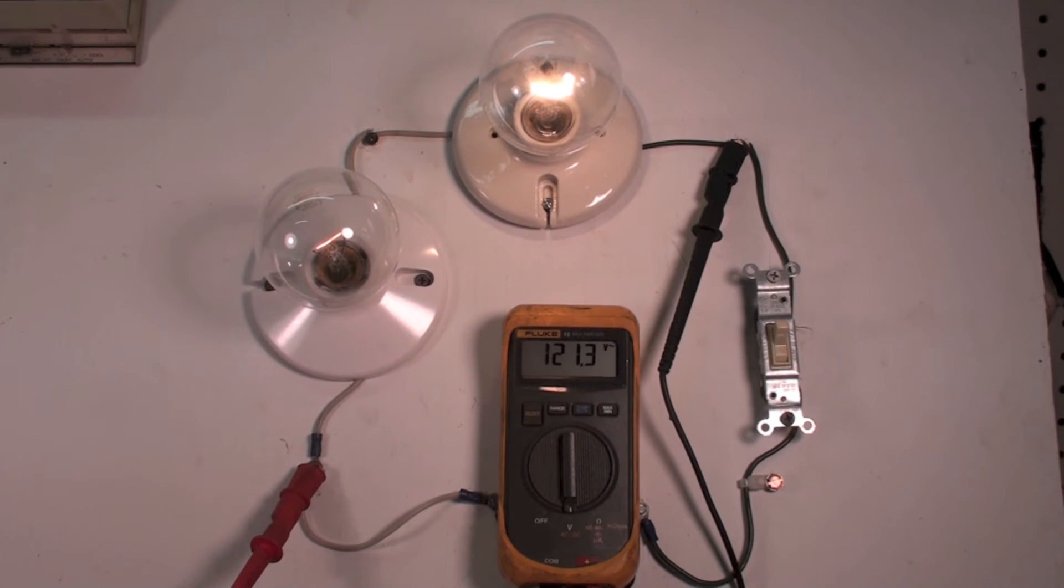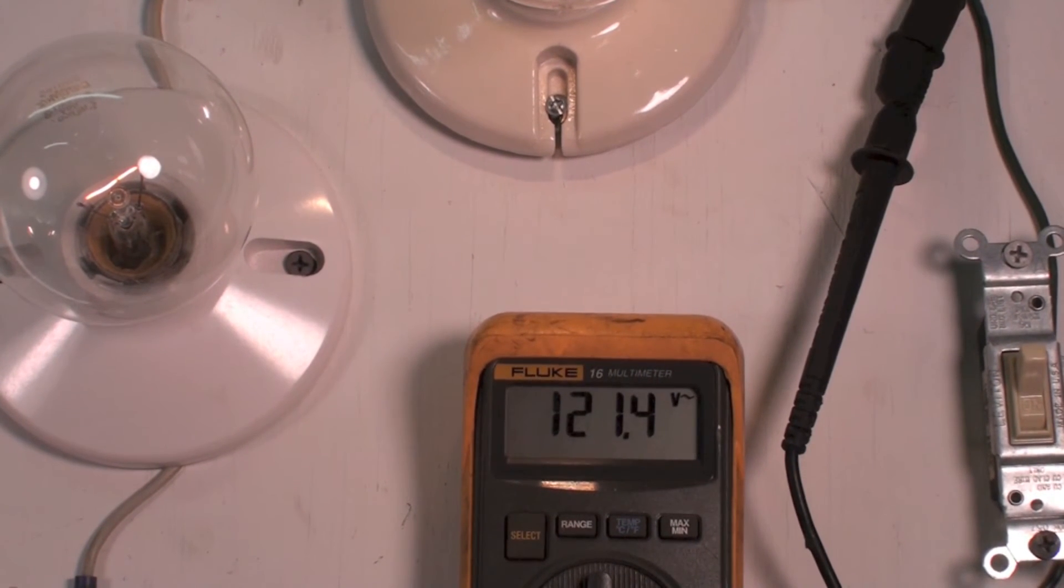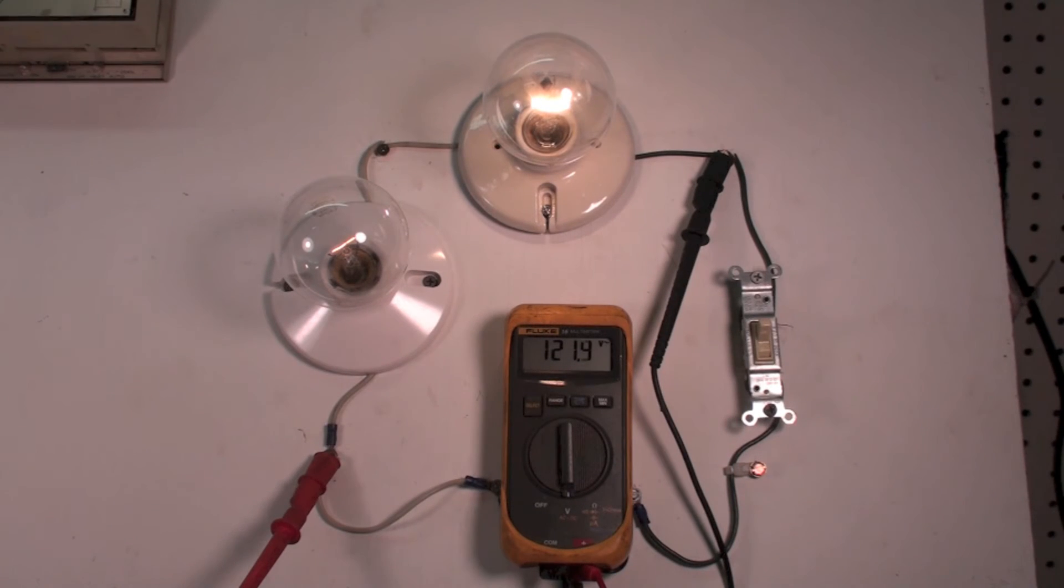So I'm either side of line, I am actually in parallel with these two loads, and I'm reading 121.3 or 121.4 volts. That's normal because I have 121 volts drop across this circuit.